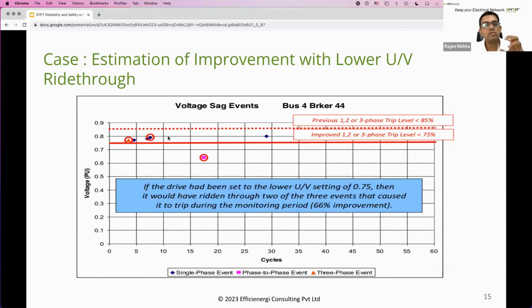This was about a cement plant where they had a typical medium voltage drive, and the drive was tripping due to occurrences of a certain magnitude of voltage sags in the plant. Over a period of 3 months, a power quality study was conducted, and the frequency of occurrence of these voltage sags was plotted, normalized over a certain period of time.